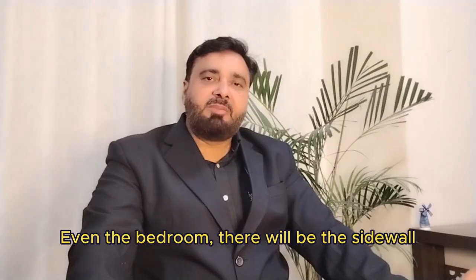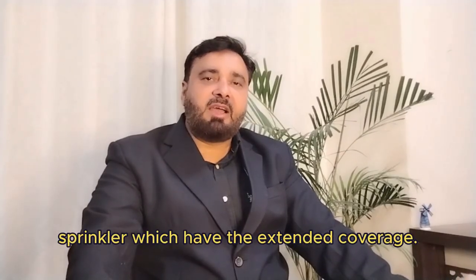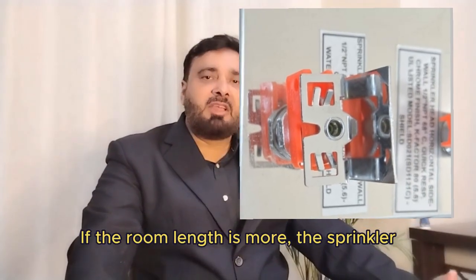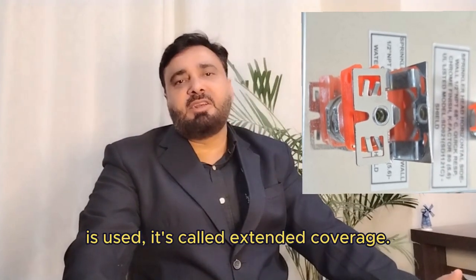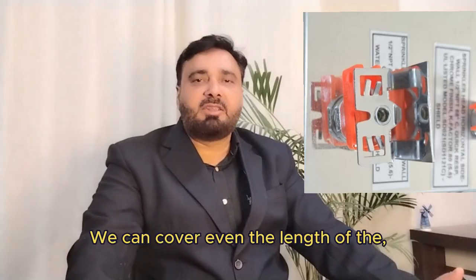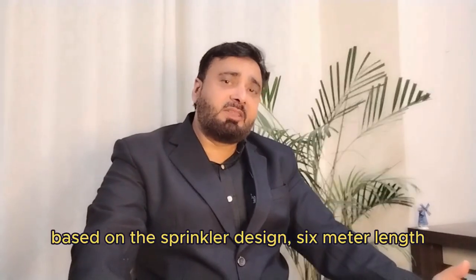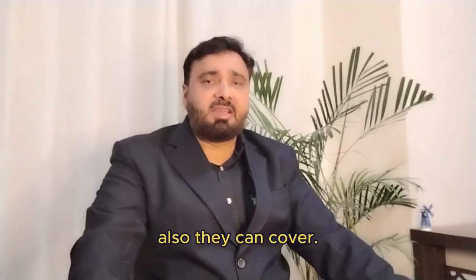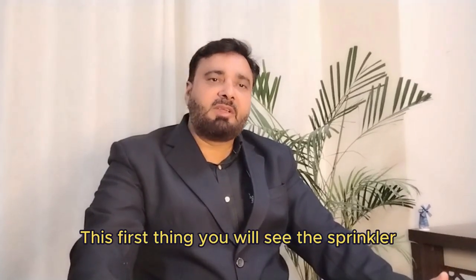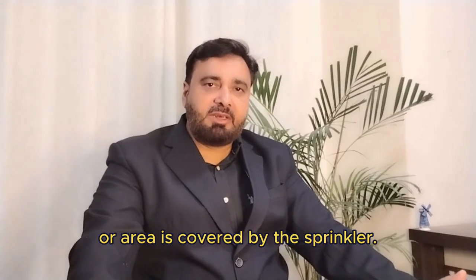Even in the bedroom, there will be a side wall sprinkler which has extended coverage. If the room length is more, the sprinkler used is called extended coverage, which, based on the sprinkler design, can cover even a 6-meter length. This is the first thing: you will see that the area is covered by the sprinkler.